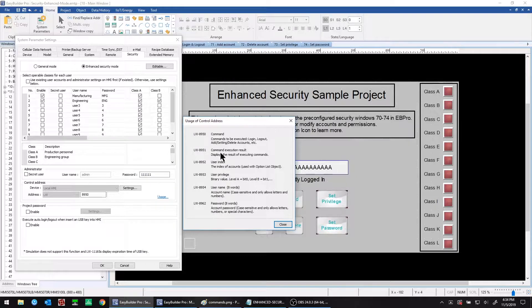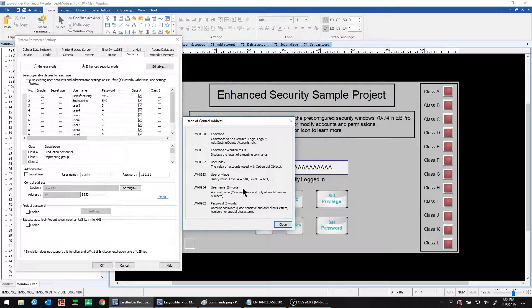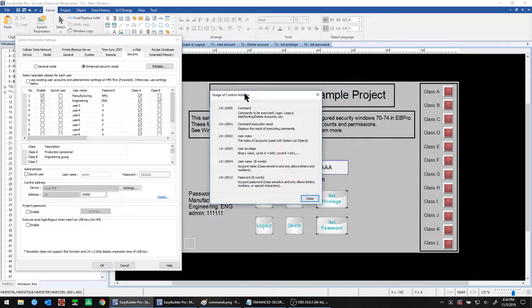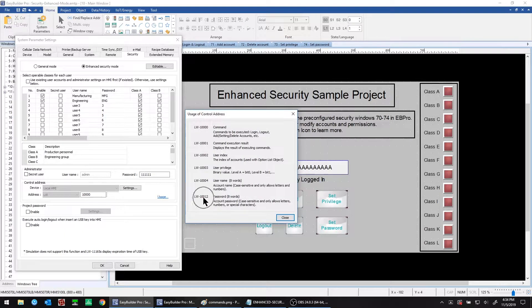The result of the command execution will be written into the next consecutive register, local word 8951 in this case. There are also user index and privilege registers, and sets of registers for username and user password — those are each eight words long. You can change this default address; for example, if you make it 10,000 and click usage again, you can see it adjusts all examples accordingly, so password would be at local word 10,012.